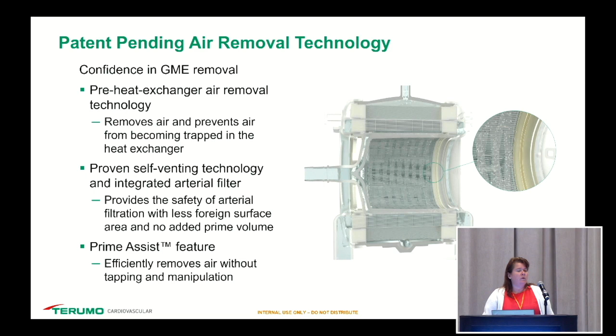So we have patent pending air removal technology. We are confident in the GME removal. We have pre-heat exchanger air removal technology. Basically, with the polymer oxygenator, before the blood even enters into the heat exchanger, there is technology that Terumo has been able to create that removes the air before it even enters the actual heat exchanger itself, and it is vented out. So basically, it's provided safe arterial filtration, less foreign surface area, and no added prime volume for that as well. And then also, as we mentioned, we have the Prime Assist feature that allows us to efficiently remove air without tapping and manipulating. With the FX series, the Prime Assist was off to the side, so there might be air that hangs up there. It may be a little bit more difficult to de-air.